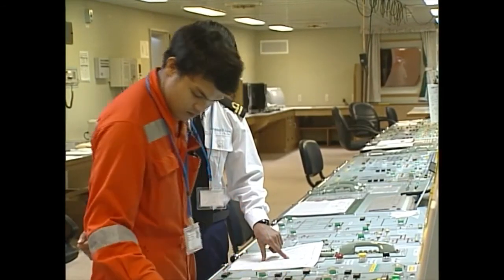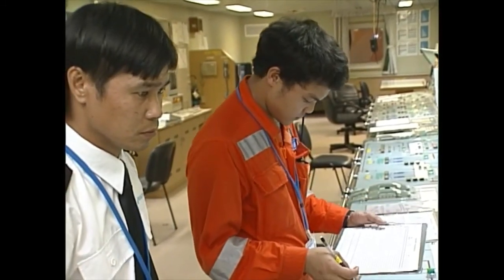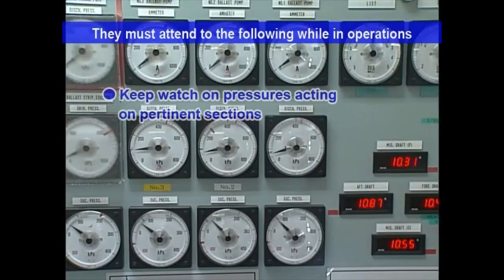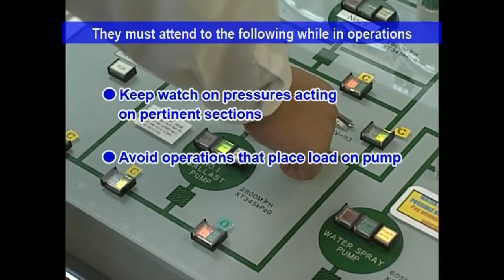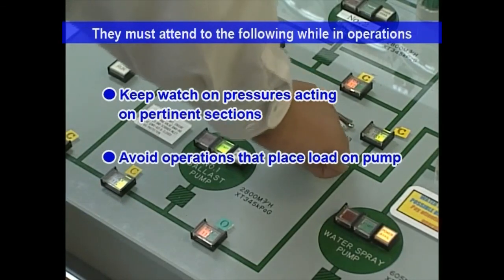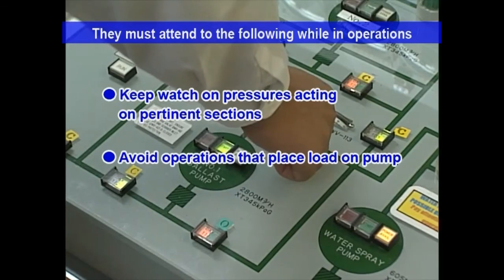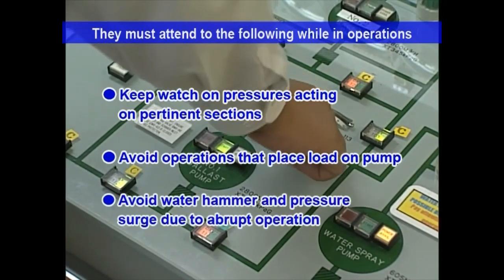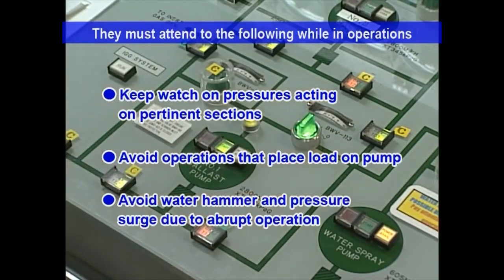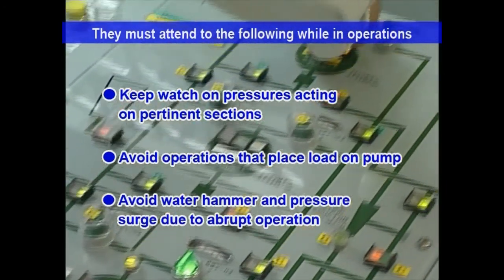Especially, they must attend to the following while in operation. Keep watch on pressures acting on pertinent sections. Understand the pump's principle and avoid load-placing operations such as cavitation and air drawing. And understand valve characteristics and avoid water hammer and pressure surge due to abrupt valve operation.